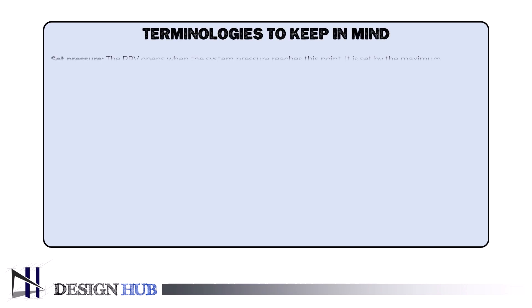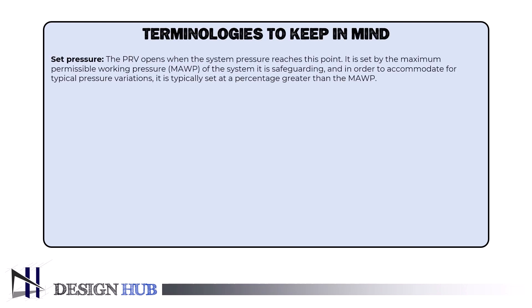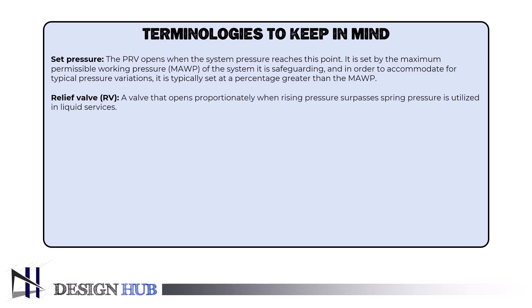Also, there are some terminologies to keep in mind when going through safety valves. The first is set pressure: the PRV opens when the system pressure reaches this point, set by the maximum permissible working pressure, MAWP, of the system it is safeguarding, and typically set at a percentage greater than the MAWP to accommodate typical pressure variations. The American Society of Mechanical Engineers, ASME, may have established recommendations for accuracy. The second is the relief valve, RV: a valve that opens proportionately when rising pressure surpasses spring pressure, utilized in liquid services.